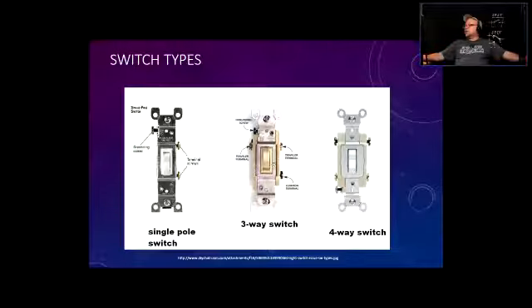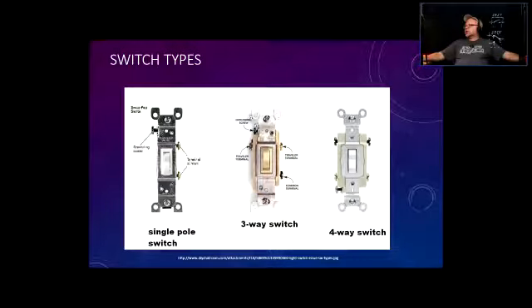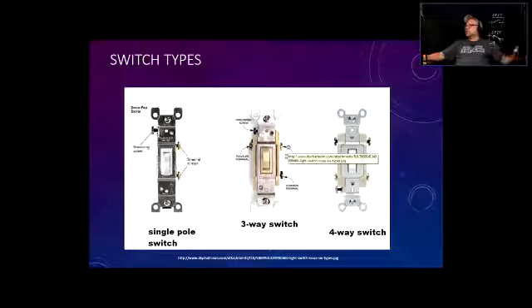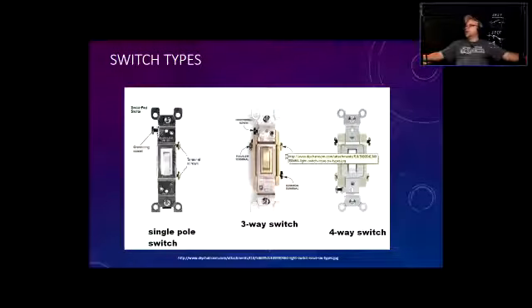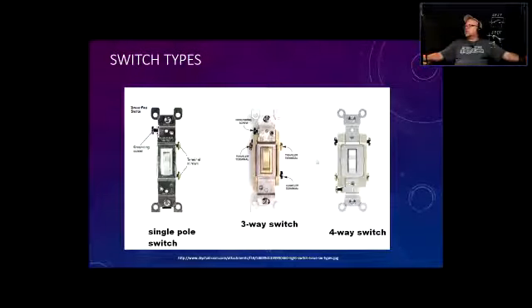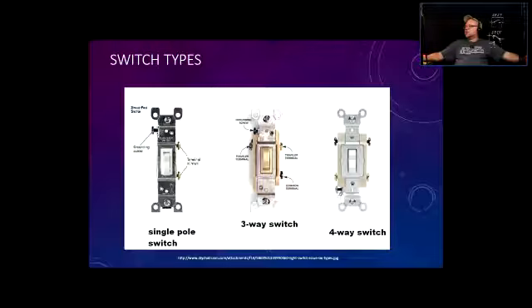When we go to more ways, this switch has a bonding or grounding screw – sometimes you don't have it. Here's a common terminal and two traveler terminals, and we'll talk about how things are connected. How many ways to get into the switch for the active wires? One, two, three – it's a three-way switch. One, two, three, four – that's a four-way switch.